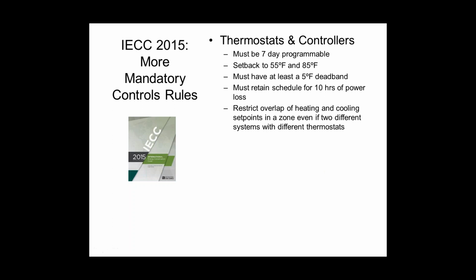You have to restrict the overlapping of heating and cooling set points, which sounds obvious because we just said you have to have a 5-degree deadband on the thermostat. But what about when you have 2 thermostats in the same room? Sometimes this happens. Sometimes you got a radiant floor in a perimeter office zone, and it's on its own thermostat, and then you have the air side cooling on a different thermostat. That's fine. You can do that, and I understand why you might want that because the radiant floor has different lag times and all that.